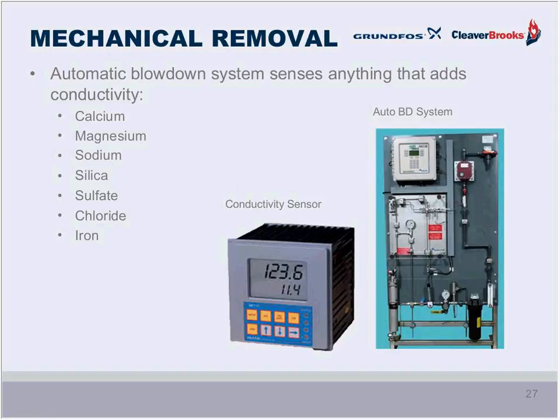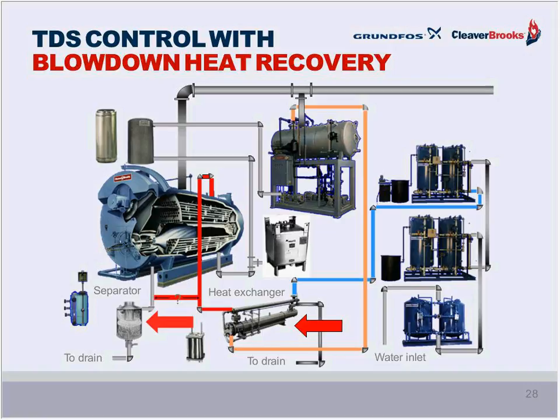And speaking of continuous blowdown, I'd be remiss if I didn't mention that in many cases this automatic blowdown results in a continuous stream of very hot boiler water, which needs to be cooled by code before entering the sewer system. We can do that by allowing the effluent to go to a blowdown separator, as shown here with the red arrow on the left, where the hot boiler water is cooled and then dumped to the sewer. But why not reclaim that heated water first by using a blowdown heat recovery system, as shown with the red arrow on the right?